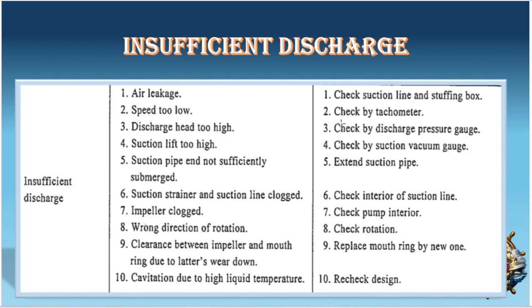Discharge head too high. Check by the discharge pressure gauge. If that is the case, then in that case you have to ensure that the things will be done correctly. Suction lift too high. Check by the suction vacuum gauge. Yes. Suction pipe end not sufficiently submerged. Yes, sometimes this is also happening. Basically, when we are using the Weldon pump, and also if manually we are doing it. Okay, so in this, if the suction end is not sufficiently submerged, then extend the suction pipe. Make sure that it is fully submerged, then only it will take the proper suction.